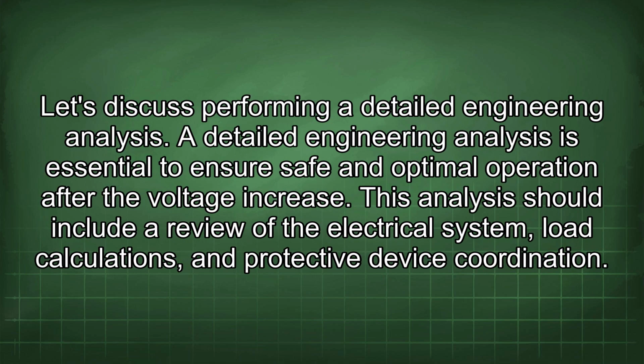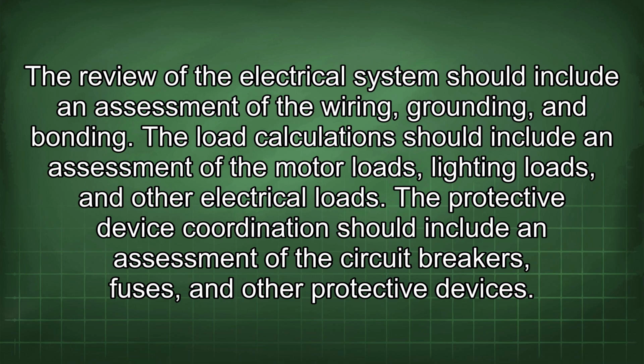Let's discuss performing a detailed engineering analysis. A detailed engineering analysis is essential to ensure safe and optimal operation after the voltage increase. This analysis should include a review of the electrical system, load calculations, and protective device coordination. The review of the electrical system should include an assessment of the wiring, grounding, and bonding. The load calculations should include an assessment of the motor loads, lighting loads, and other electrical loads. The protective device coordination should include an assessment of the circuit breakers, fuses, and other protective devices.